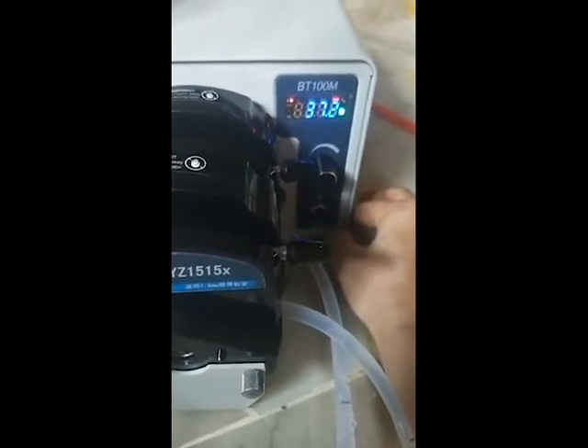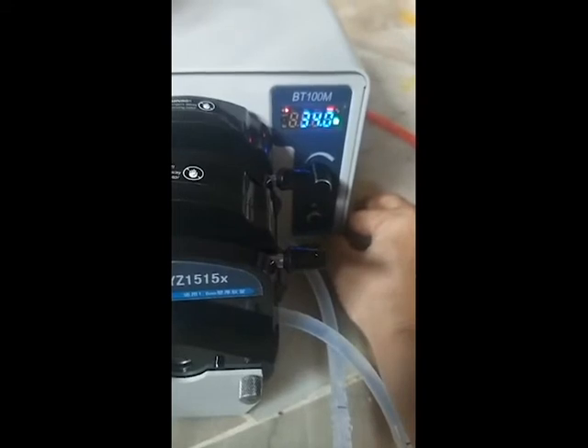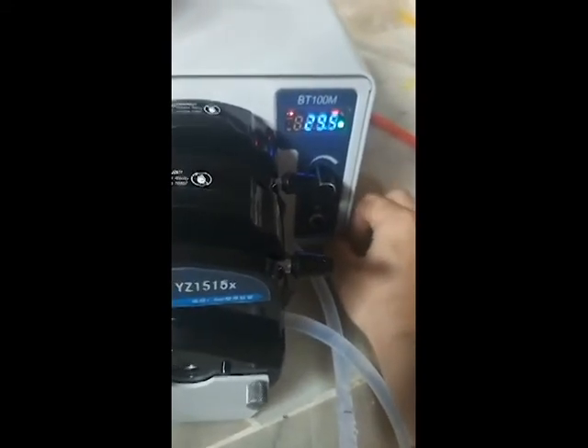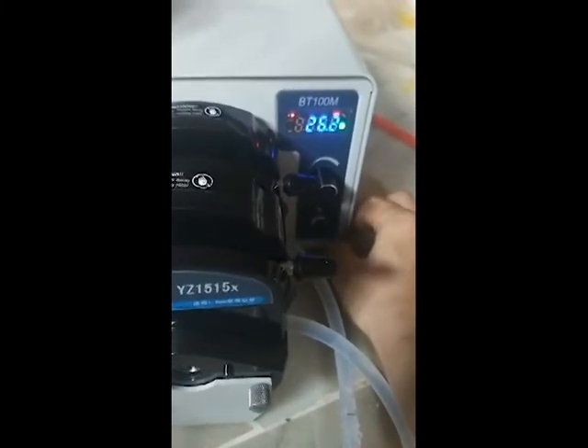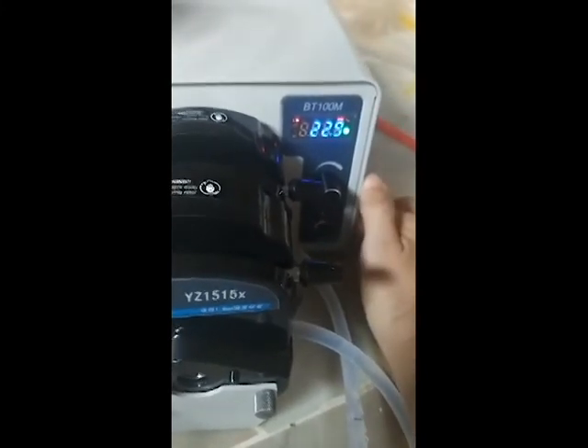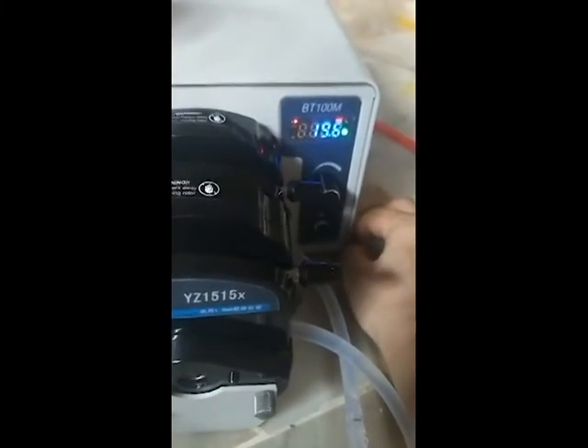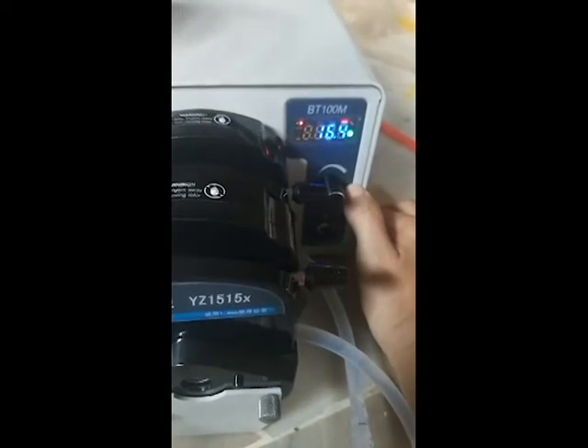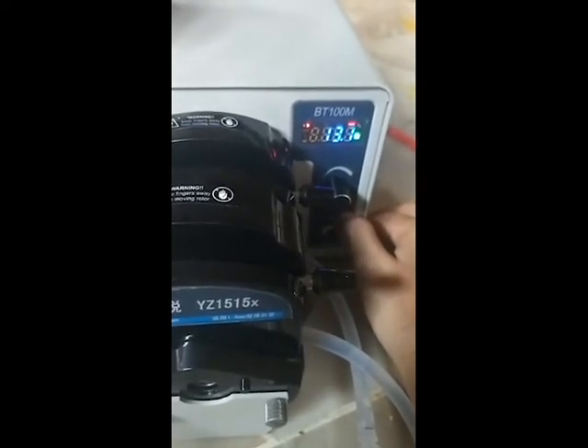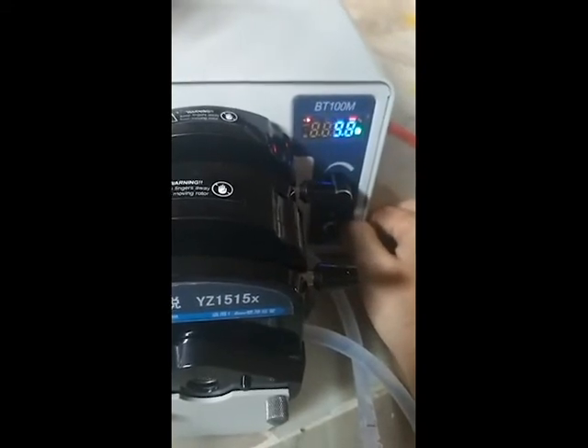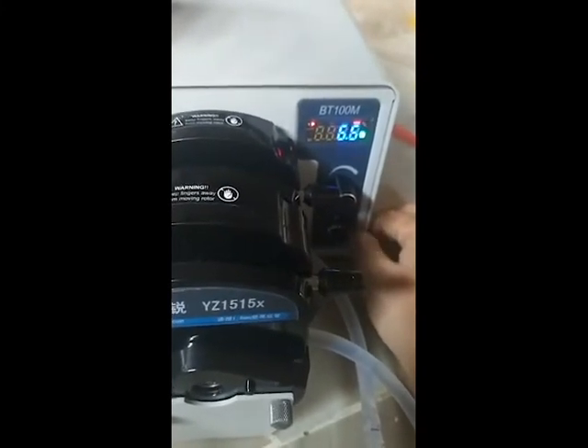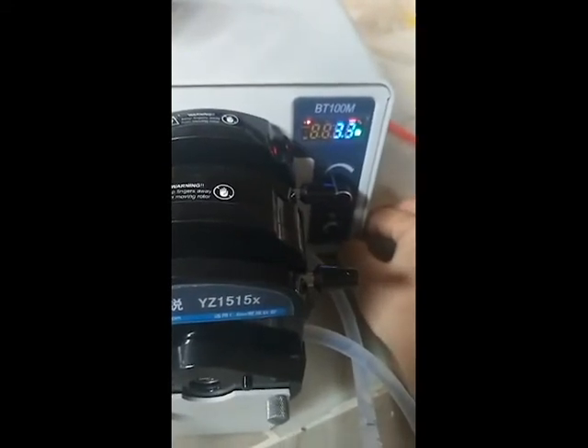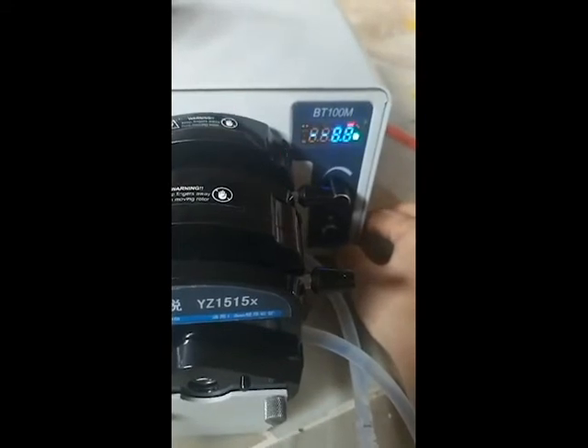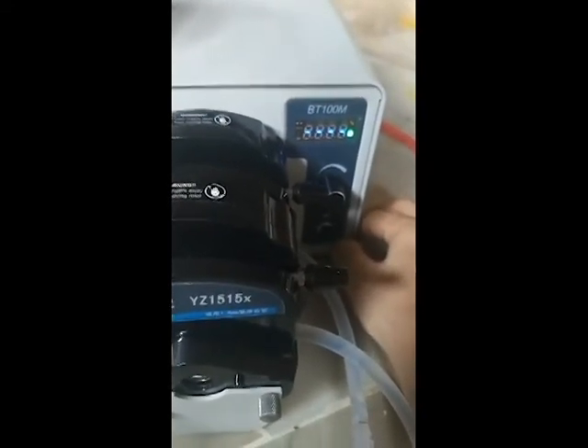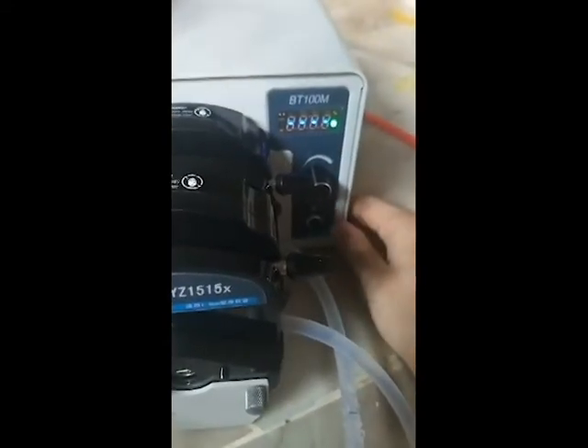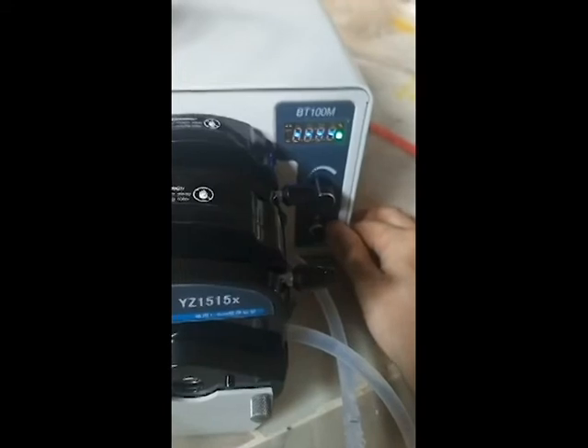How to calibrate? You can measure 1 milliliter of your target liquid, then check the weight. Based on that weight, you can get the density of your liquid. After you finish the collection of this liquid, you can use that density and the total weight of the collected liquid to get the real volume of your target liquid. At this moment, the balance must be very high accuracy, maybe accurate to at least 0.1 milligram. Then that balance can be used to calibrate this pump. And of course, you need to make sure your balance has been calibrated with high accuracy.